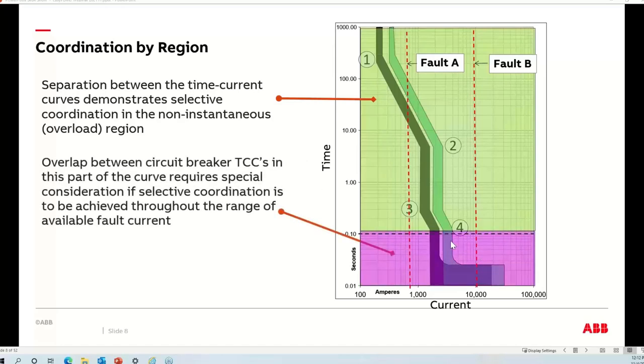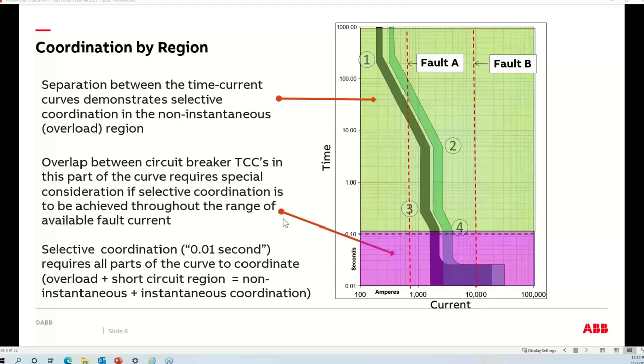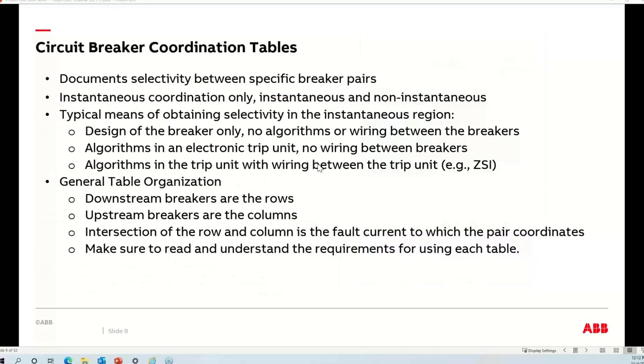Once I go below that point into the instantaneous part of the protection — especially that pesky foot of the breaker that tends to overlap in most cases — it's really a different skill set. What it comes down to is needing a vendor coordination table to discern if I can get coordination in this area. When we say selective coordination per the code definition, or the informal industry term of 0.01-second coordination, both colored regions have to coordinate out to whatever the maximum available fault current is.